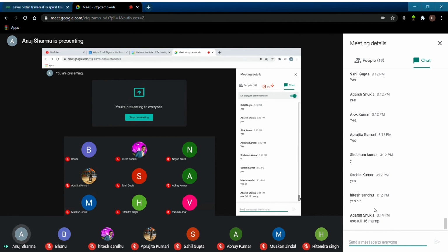Yes, use full range of your 4 to 20 milliamps. So when you are just observing for a short range of your 4 to 20 milliamp, what can you do in order to use your full 4 to 20 milliamp range? For example, for a particular process, we are only getting fluctuations from, say, 8 to 20 milliamps, or you can say 8 to 15 milliamps. Then what should you do?